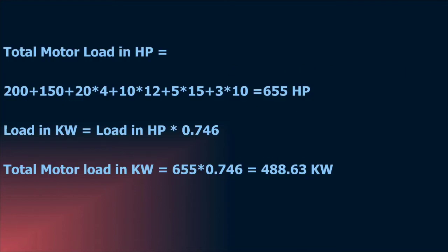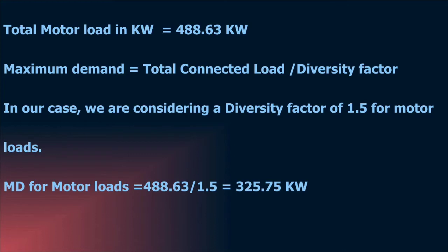And now coming to our example, the total motor load in HP will be 655, and it is converted to kilowatt by multiplying with 0.746, which gives the value of 488.63 kilowatt. In order to arrive at the maximum demand value, we have considered the diversity factor for the motor loads to be 1.5, which gives the maximum demand as 325.75 for the motor loads.